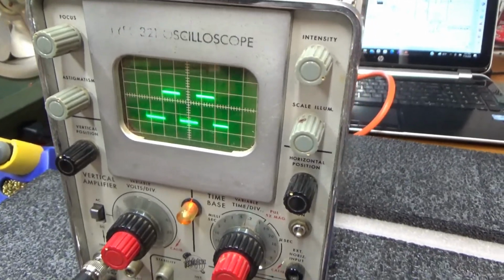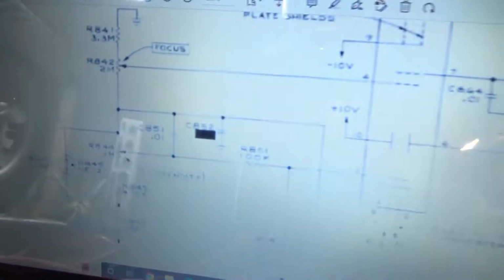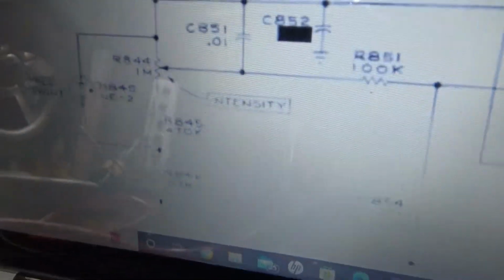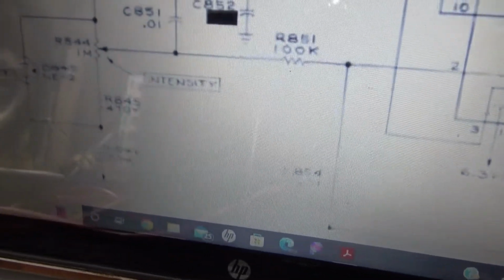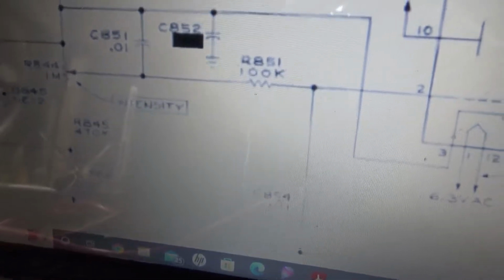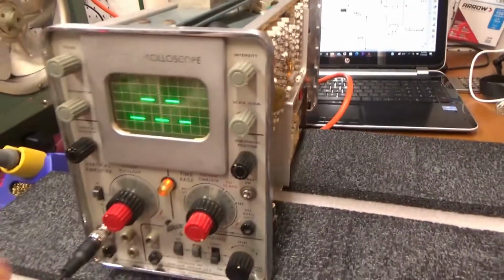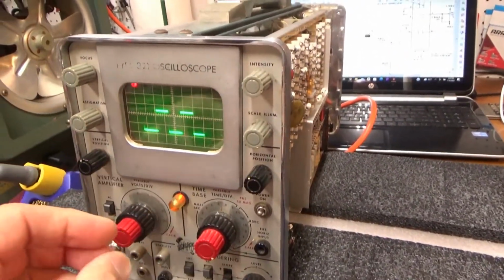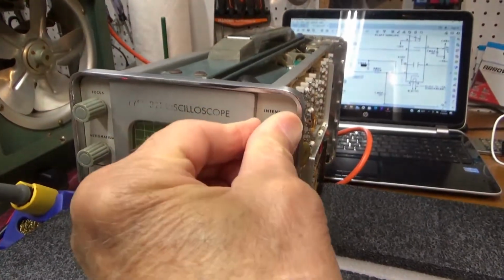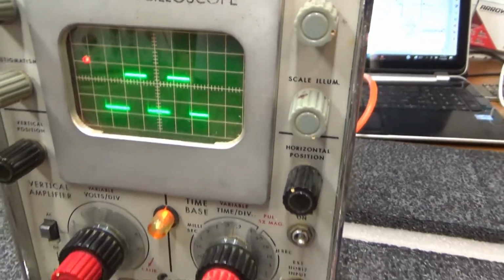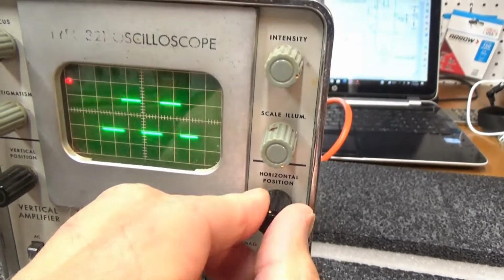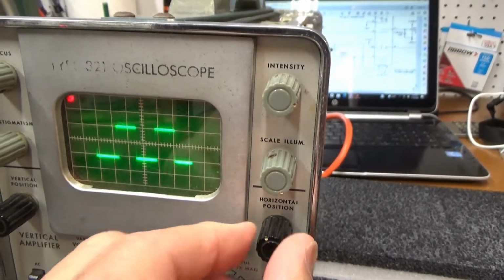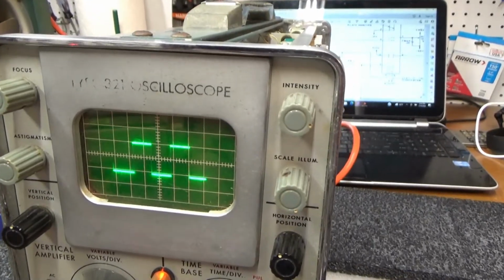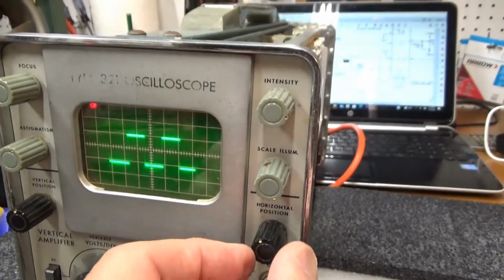Okay, the flashing seems to have gone away. I noticed that there's the pilot light right there, and that was flashing, and in connection with that there's the intensity pot and the focus pot. So I just played with both of those, wiggling them back and forth, and that seems to have gotten rid of the blinking of the display. Now that's working fine. It's not the full width of the CRT, so that's an adjustment or something, but see, it's still blinking a little bit.